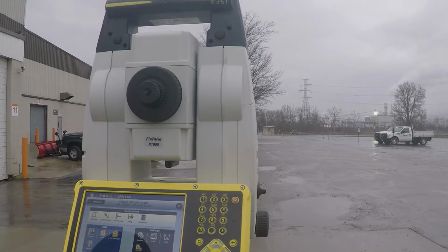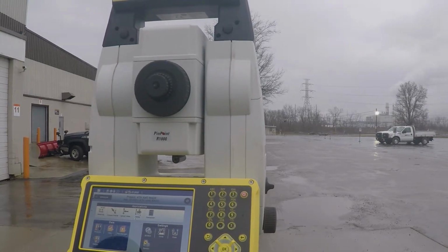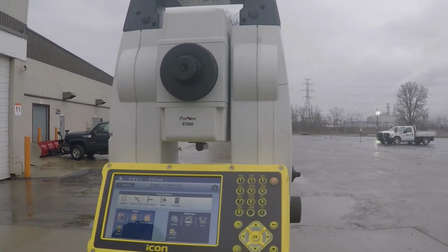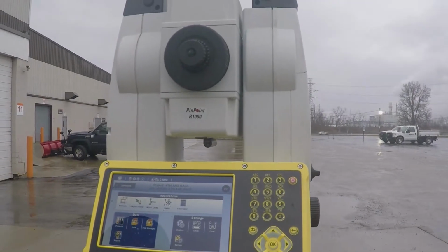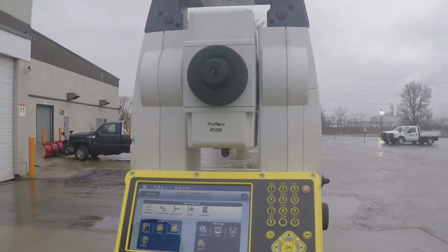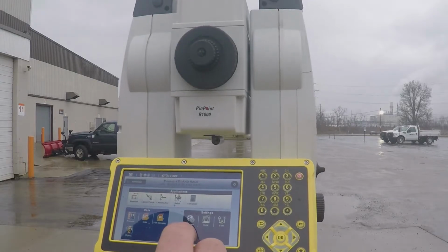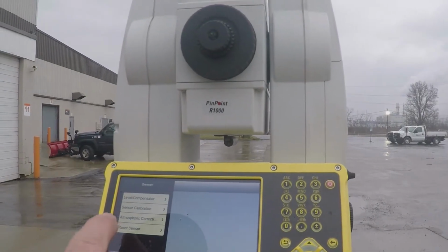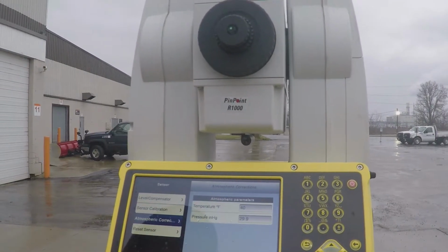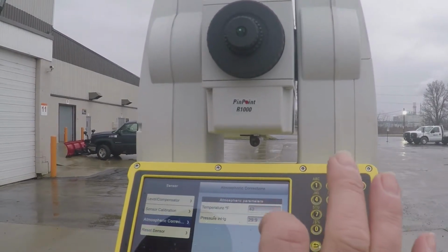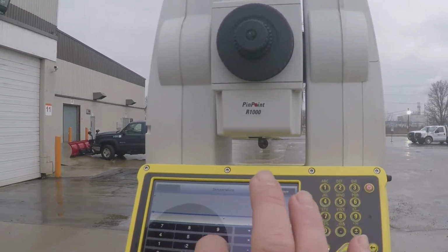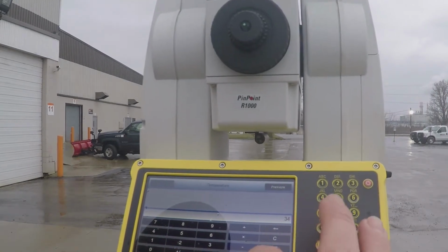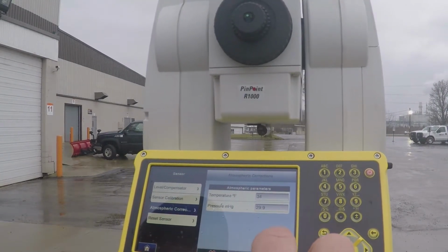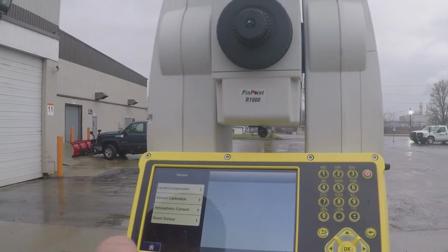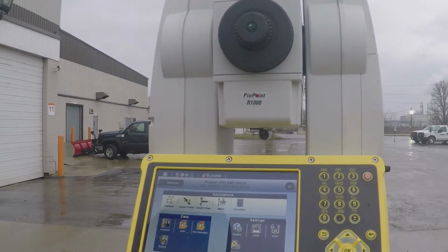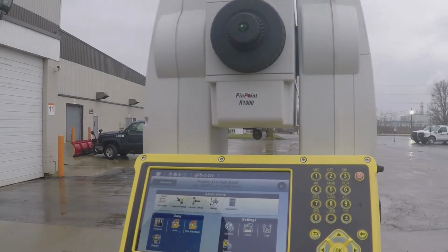We got the robot set up here. We got the robot turned on and we're on the home screen. So to do a field calibration, I guess first we'll just make sure our temperature's set. So we're going to go through the sensor, then we're going to go to the atmospheric corrections, and it's 40 degrees. I think in the truck it said it was 34. So we're going to type in 34 degrees and we'll leave the pressure alone. And we should be good, ready to go to the field calibration.